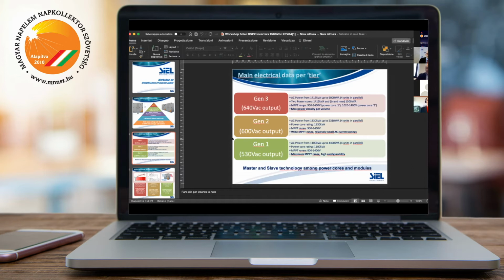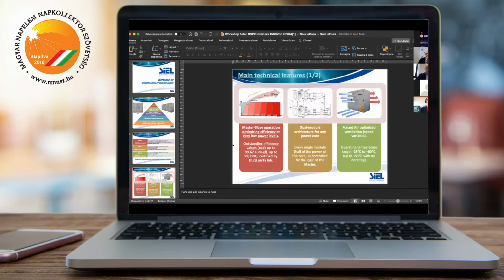These characteristics are not really important when we design the output, but are extremely important, like some of my colleagues were saying before, when we connect with the PV modules, with the solar modules, because we could increase the power from 1,100 kVA up to 1,400. So as you can see, there is over 300 kVA more power just by using the different energy coming from the DC.